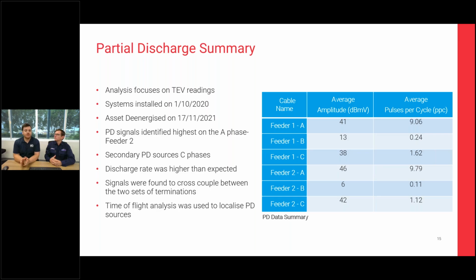On feeder 2A we were seeing 46 decibels, a very high level, but 9.79 pulses per cycle, which is a lot higher than we were expecting for that type of defect—we expected closer to 2 pulses per cycle, the normal bracket for an internal void. Having it sit higher made us start to think: was it degrading in a way we weren't expecting?